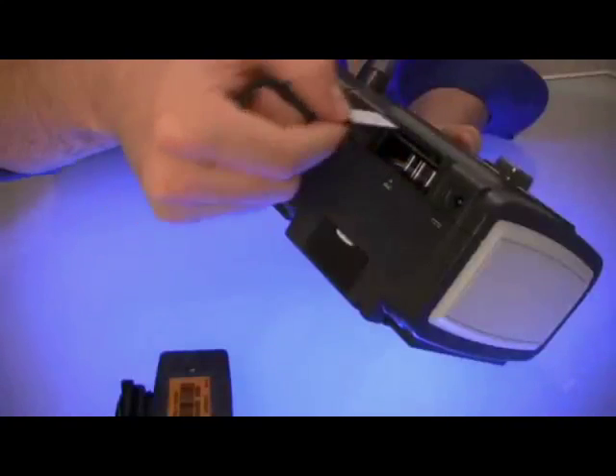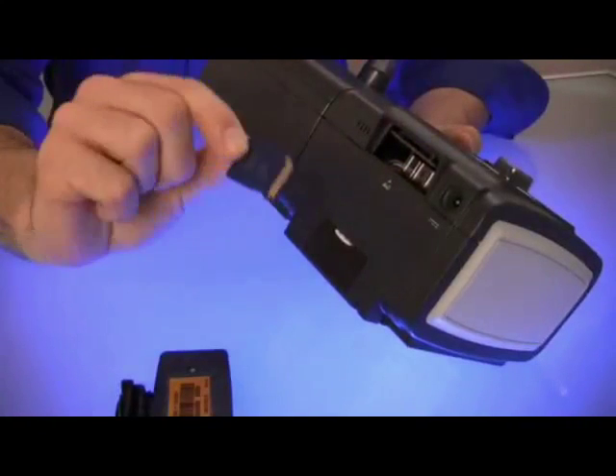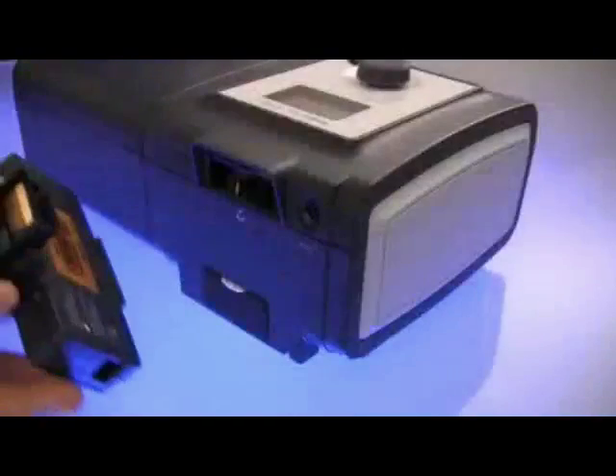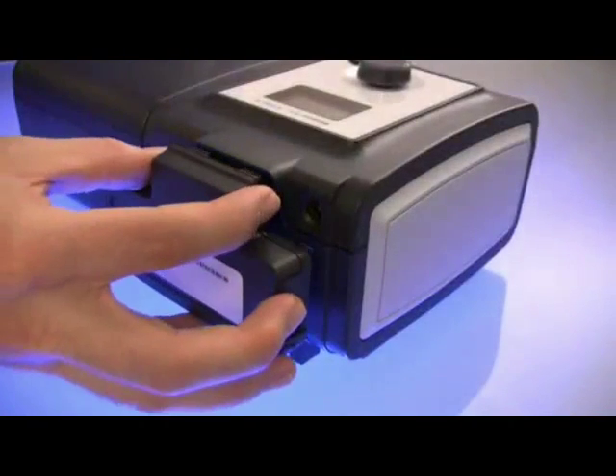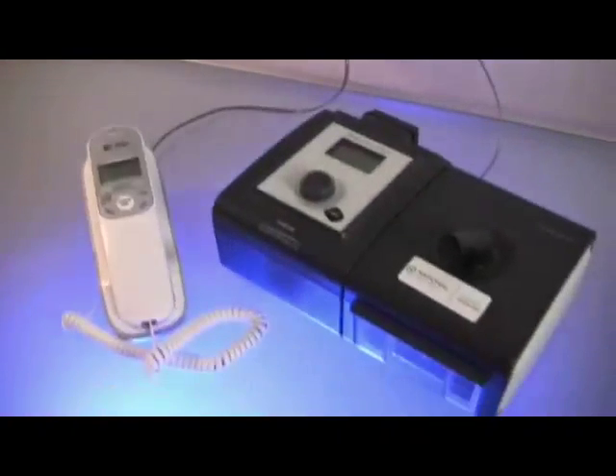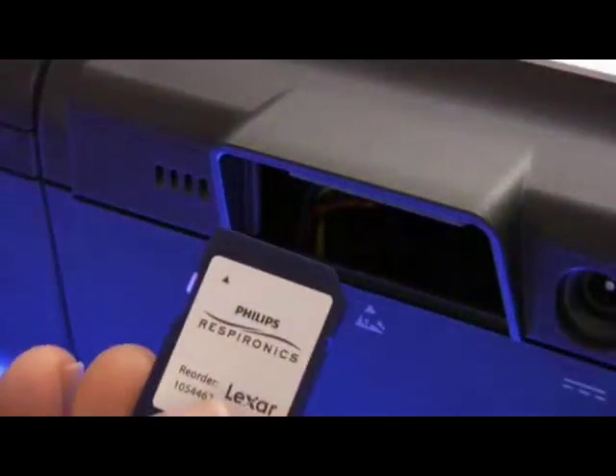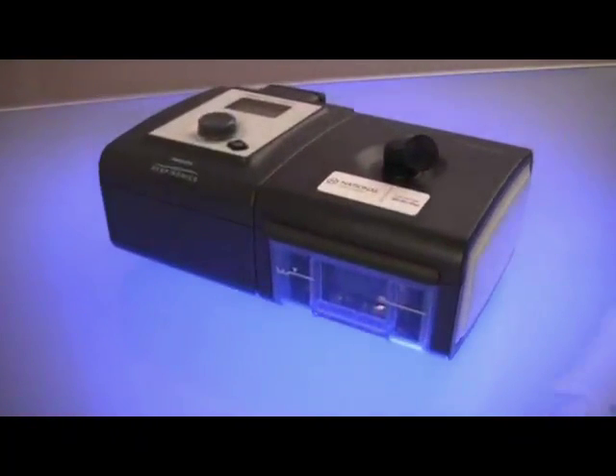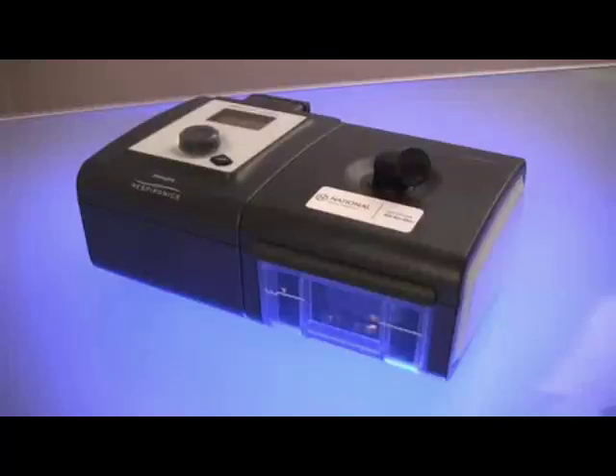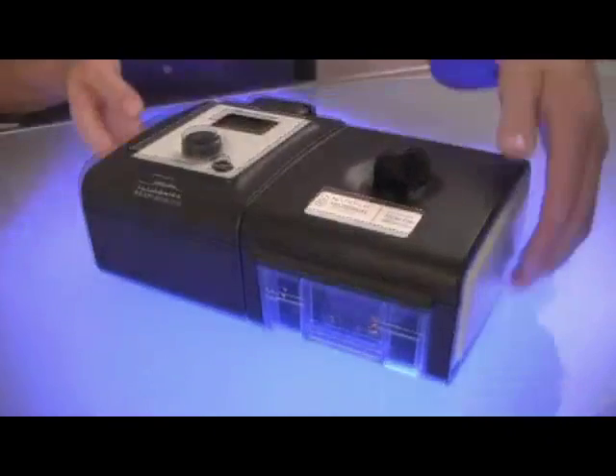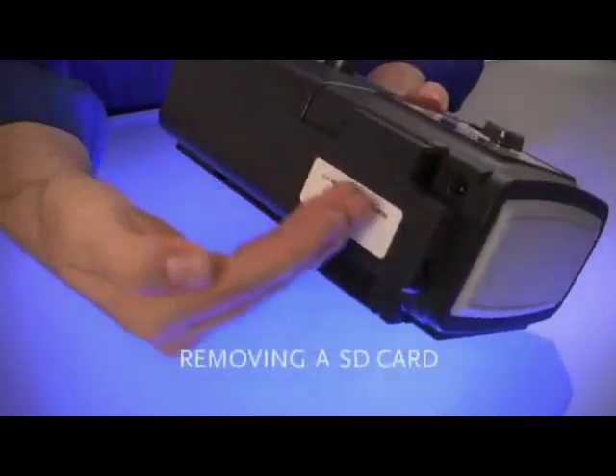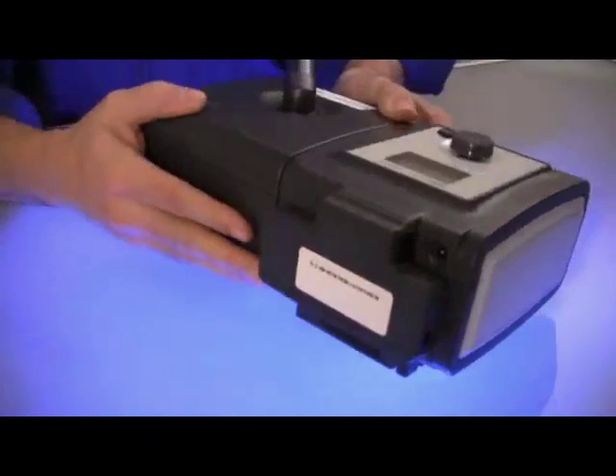This segment will explain how to access the SD card on a Philips Respironics System 1 machine that also has a modem module. If your CPAP, auto, or bi-level machine has a modem feature that connects to your phone line, your machine also has an SD card as a backup data recording device. There may be times when National Sleep Therapy or your doctor will need to retrieve data from the SD card inside your machine. This Philips Respironics System 1 machine has a modem module attached to the back, which prevents easy access to the SD card.